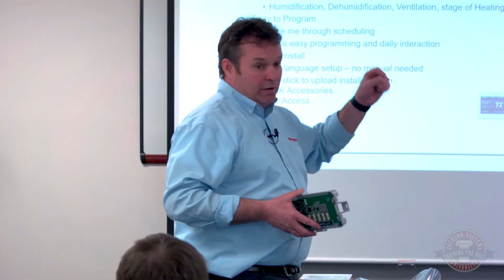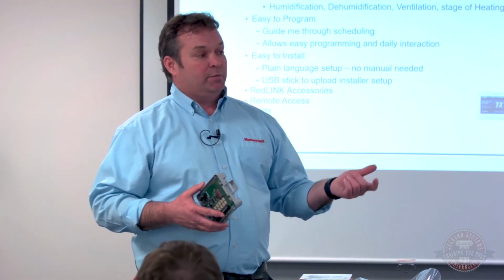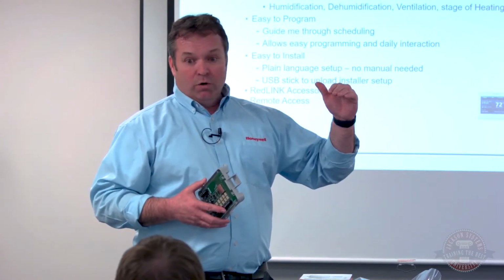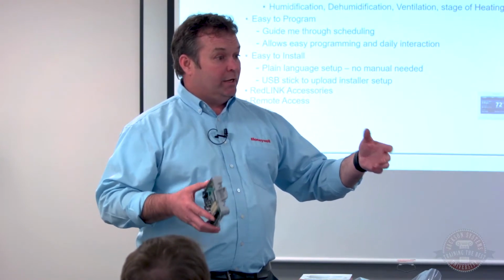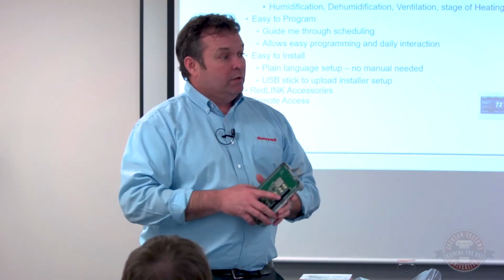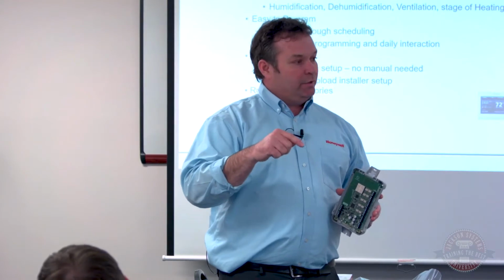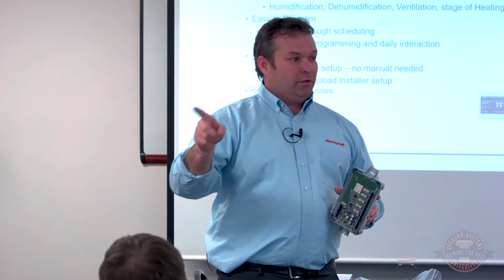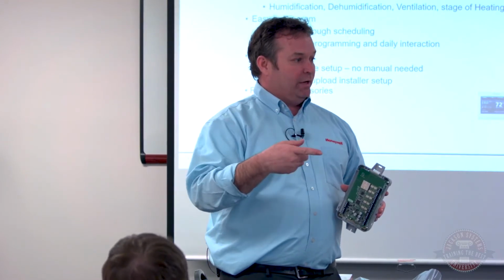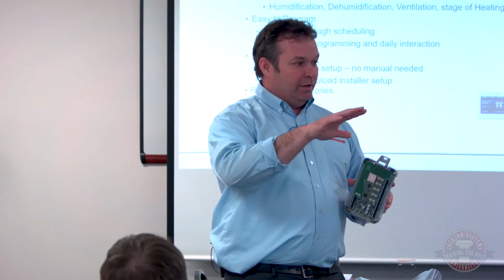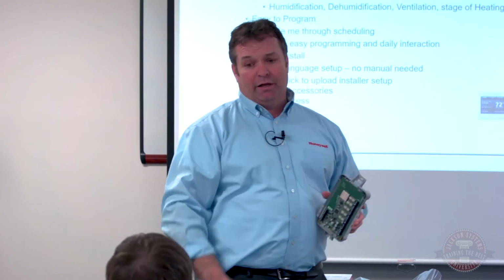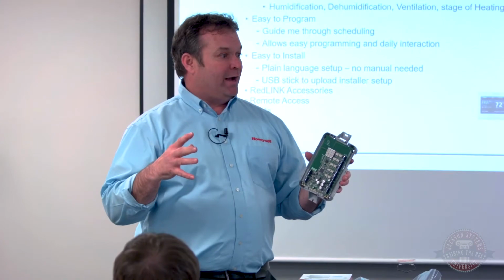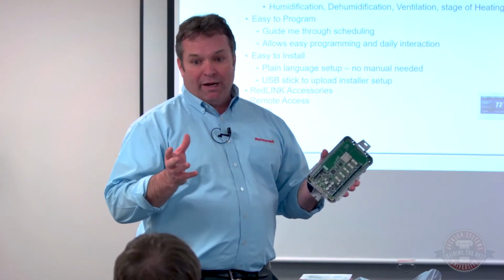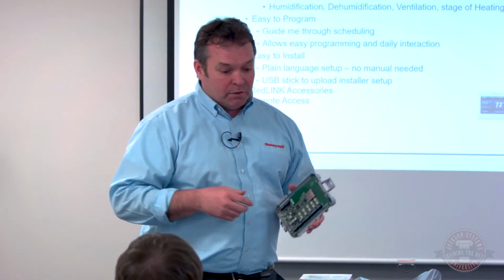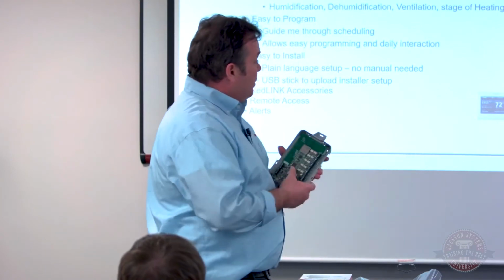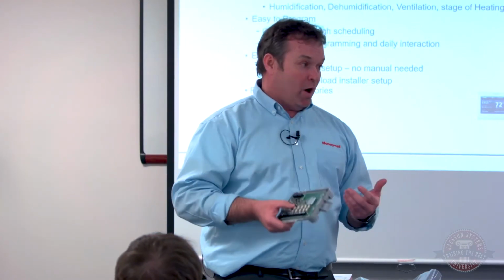The other sensor that's in the supply, I can tell the thermostat, if my coil was to ever get cold, let's say I had a Freon leak and my coil started to freeze up, you could say, well, if it gets to this temperature in there, go ahead and shut the compressor off, but leave the fan running, so by the time my tech gets there, it's going to be thawed out. It's never really going to let it get into a big ball of ice, which will cause more damage than the Freon leak, okay? And then with both of them in there, I can do delta T monitoring.